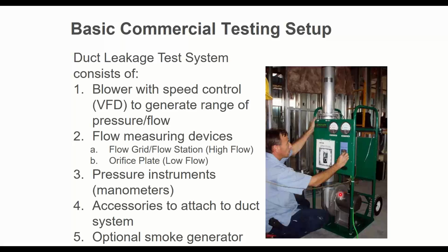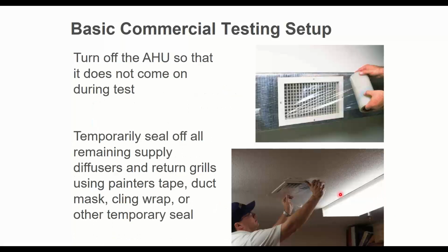If you're going to do the duct testing on a commercial system, what that essentially means is you're going to bring in a portable fan of some sort, like this gentleman has here, that has a speed control on it. And you're going to put airflow monitoring stations on there. You're going to suck air from the room and shove it into the ductwork while you simultaneously have taped off all the ductwork. I know my pictures here are a little more residential-ish, but one's a lab actually, and one looks more like it's residential. But you're gonna tape off all the ducts, all the diffusers, so air cannot come out the diffusers.